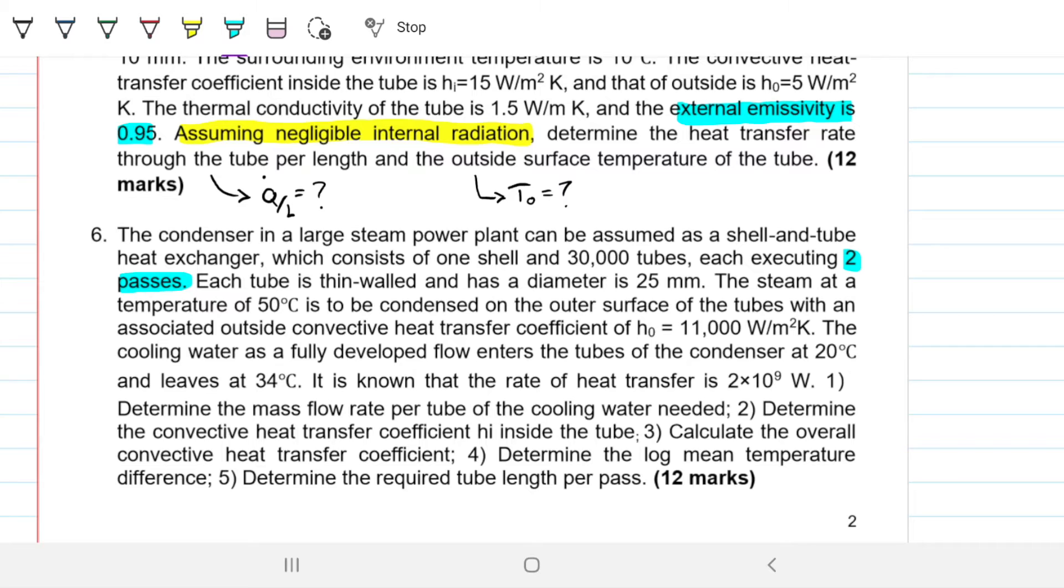The cooling water, as a fully developed flow, enters the tubes of the condenser at 20 degrees Celsius and leaves at 34 degrees Celsius. It is known that the rate of heat transfer is 2 times 10 to the 9 watts. 1. Determine the mass flow rate per tube of the cooling water needed. 2. Determine the convective heat transfer coefficient, HI, inside the tube. 3. Calculate the overall convective heat transfer coefficient. 4. Determine the log-mean temperature difference. And 5. Determine the required tube length per pass.